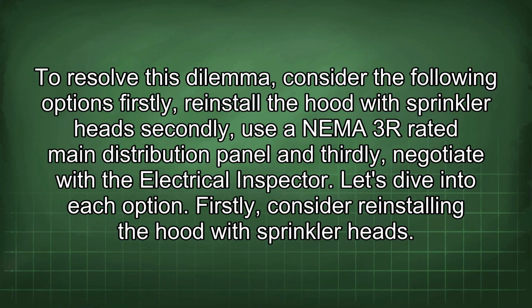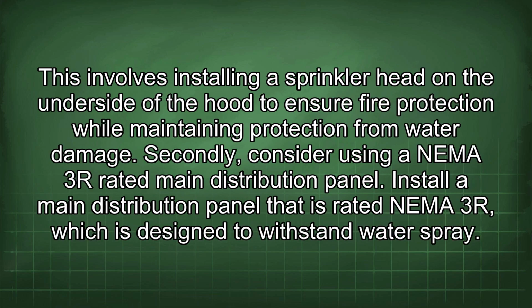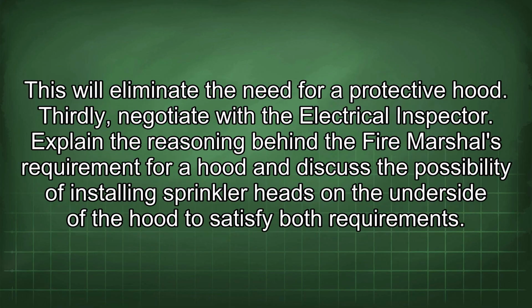Firstly, consider reinstalling the hood with sprinkler heads. This involves installing a sprinkler head on the underside of the hood to ensure fire protection while maintaining protection from water damage. Secondly, consider using a NEMA 3R rated main distribution panel. Install a main distribution panel that is rated NEMA 3R, which is designed to withstand water spray. This will eliminate the need for a protective hood.